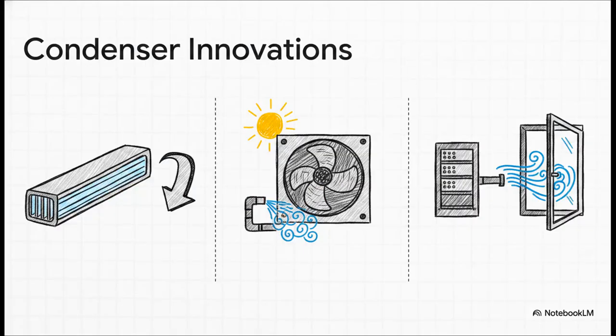It is an incredibly difficult trade-off to manage. But engineers are innovating rapidly to conquer this PUE versus WUE dilemma. Let's look at 3 cool trends. First, microchannel technology. This replaces bulky copper tubes with flat aluminum ones. It shrinks the condenser size and actually reduces chemical refrigerants by up to 40%.